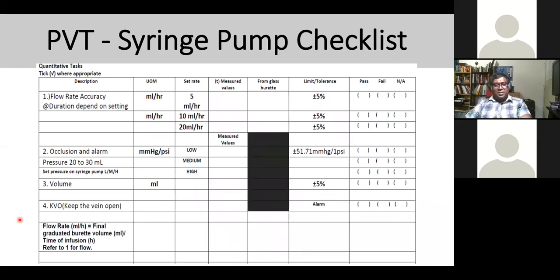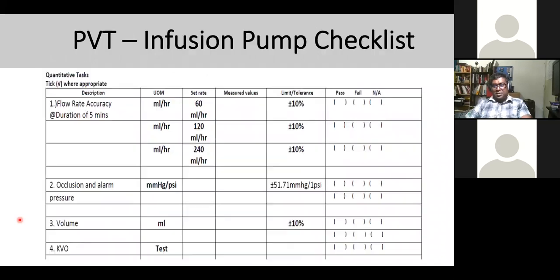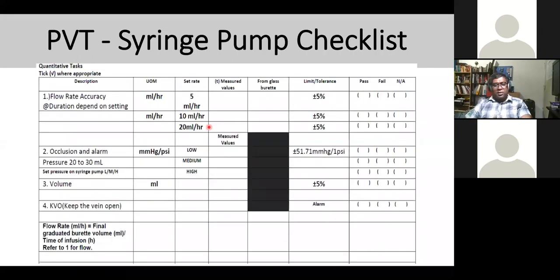So these are for the syringe pump checklist, and the other one is for the infusion pump checklist. But it's the same method, actually. The only thing is the flows are bigger on the infusion, on the volumetric pump. The volumetric can go up to 240, and accuracy about 10%. And now, troubleshooting and corrective maintenance.